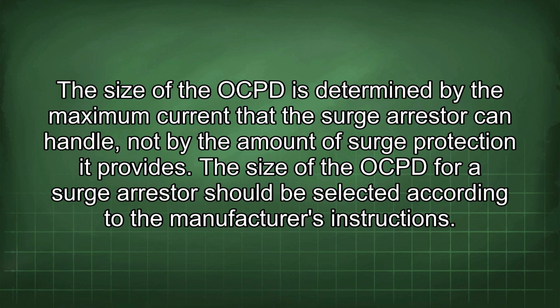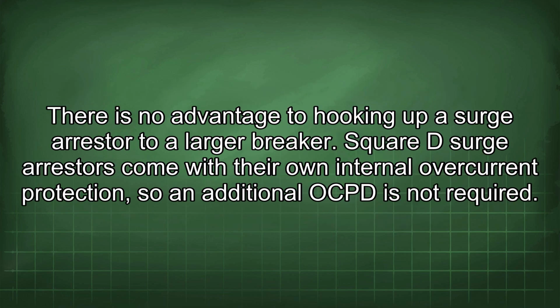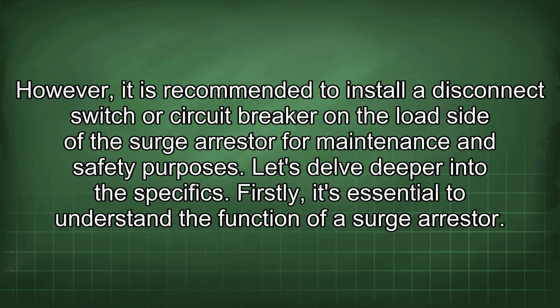The size of the OCPD for a surge arrestor should be selected according to the manufacturer's instructions. There is no advantage to hooking up a surge arrestor to a larger breaker. Square D surge arrestors come with their own internal overcurrent protection, so an additional OCPD is not required. However, it is recommended to install a disconnect switch or circuit breaker on the load side of the surge arrestor for maintenance and safety purposes.